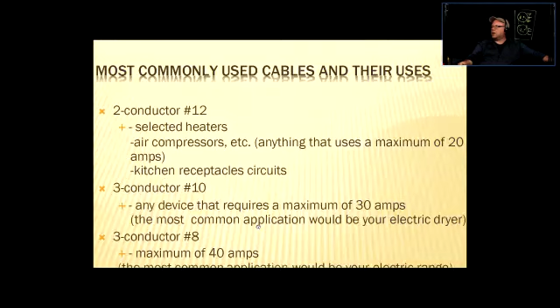All right, most commonly used cables and their uses. For 12.2, right? Selected heaters. Heaters need more current. They take more current from the receptacle. So if you need more current, you should increase the circuit breaker, but not only that. If you increase the circuit breaker ampacity, and if you do not make the wires thicker, then those wires can heat up to the point that they can actually start a fire.